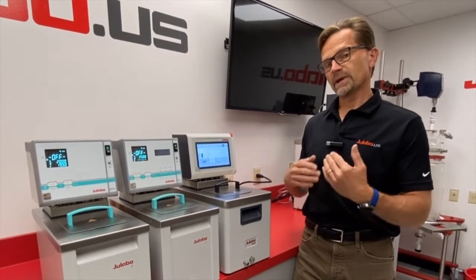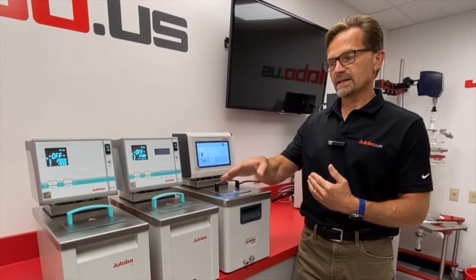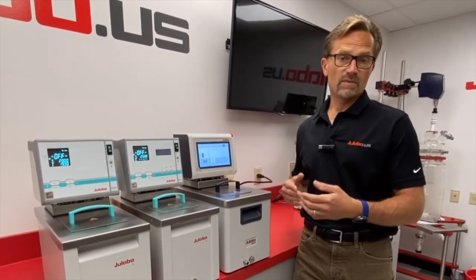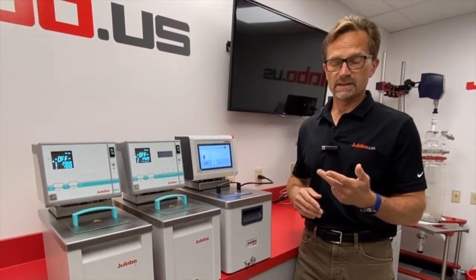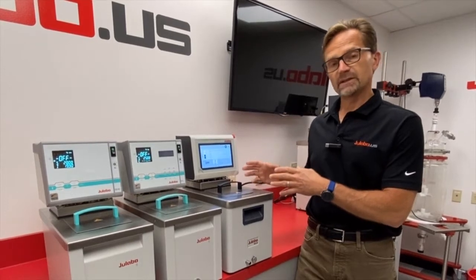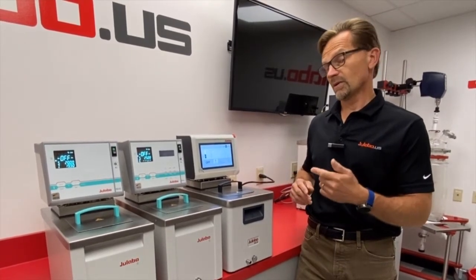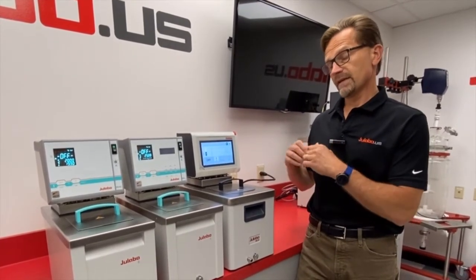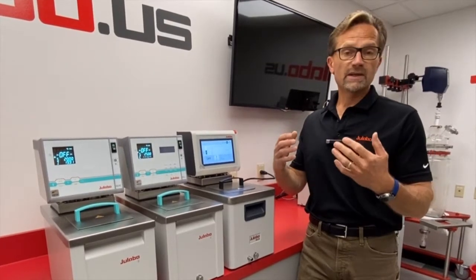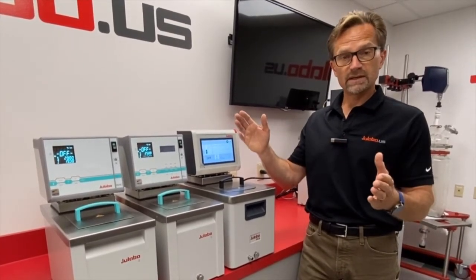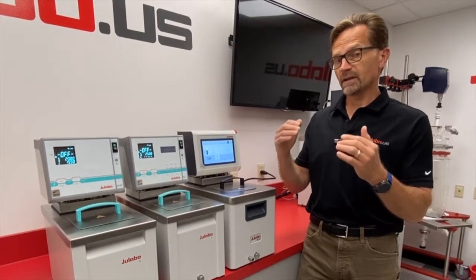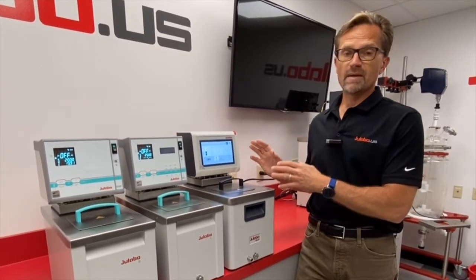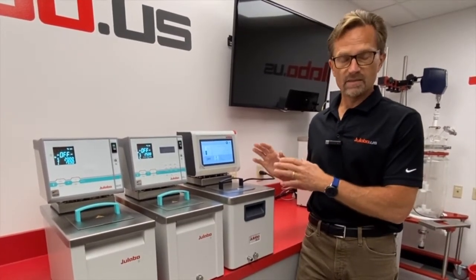Additionally, from a calibration perspective, the SE and the SL can be calibrated with either 1, 2, or 3 points, while the MAGIO MX unit can do 1, 2, or up to 10 points. So if you have an application where you need to calibrate across a broad temperature range, or you want to have a lot of data points, the MAGIO MX gives you a much tighter calibration capability.